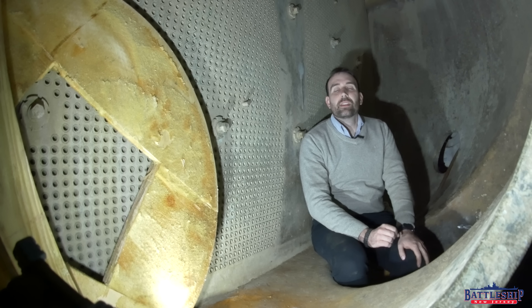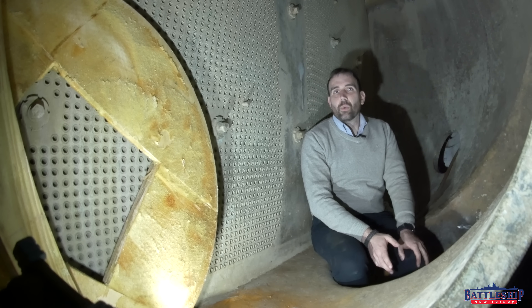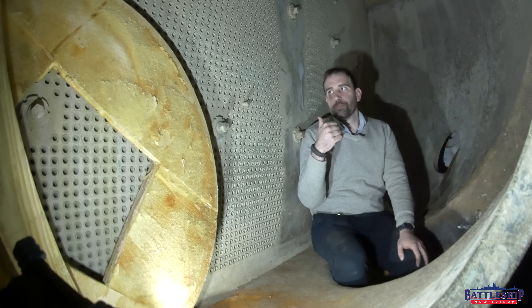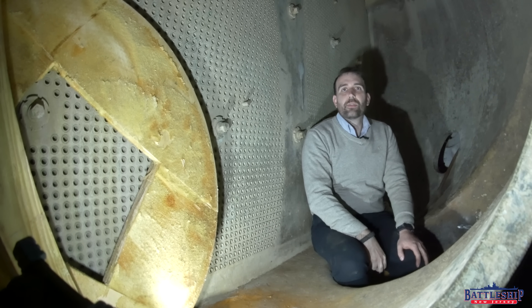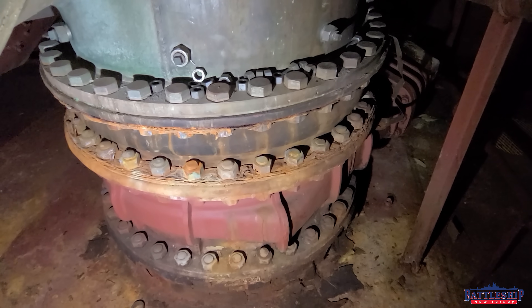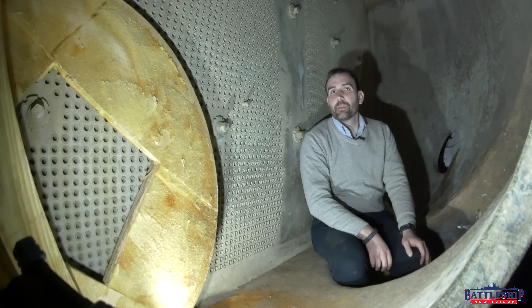We are in the discharge for number four main condenser in engine room number three. We've done a video on this particular one in the past, linked in the description below. The condensers are taking in cooling water to turn dead steam from the turbines back into boiler feed water. The cooling water comes in on the other side of the condenser, passes through these water tubes, and then the much warmer cooling water is discharged through this pipe below me. This pipe has a huge valve on it, and it has a plate welded onto the bottom of the ship that's blanked over.